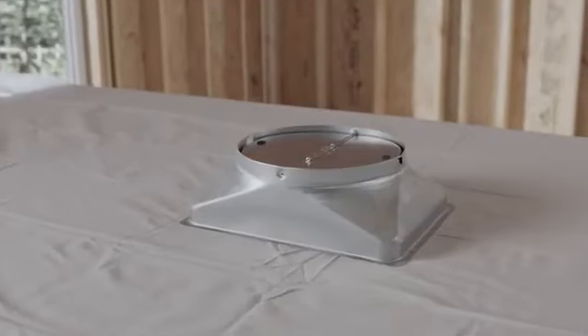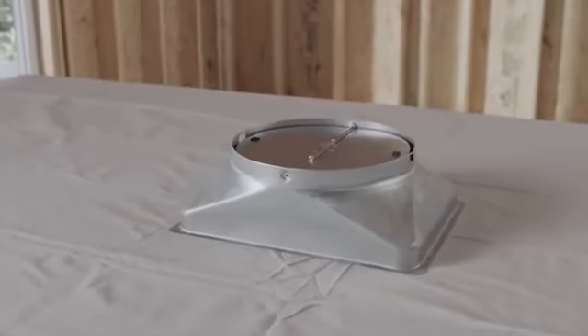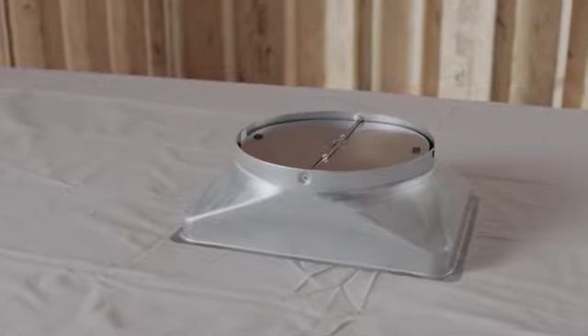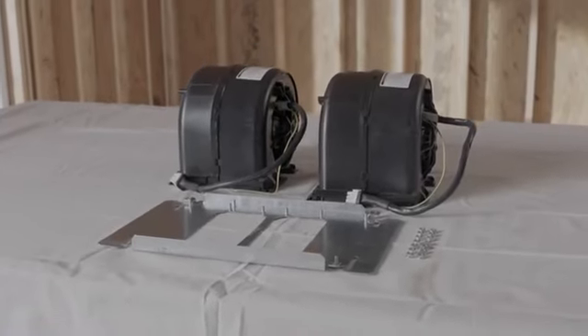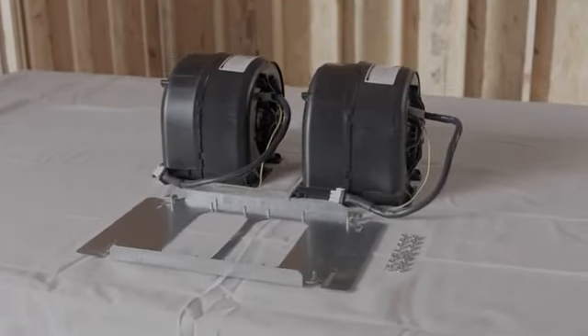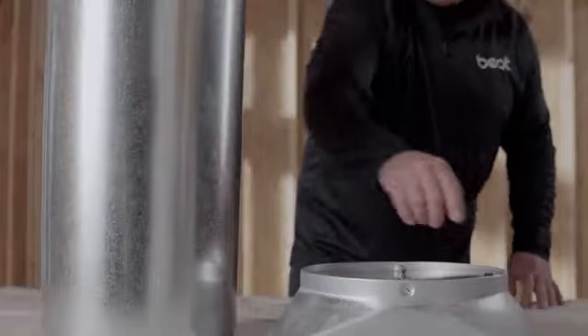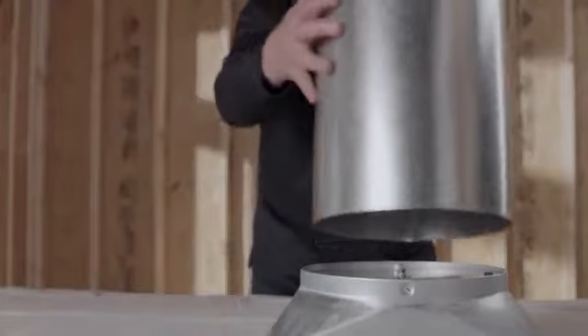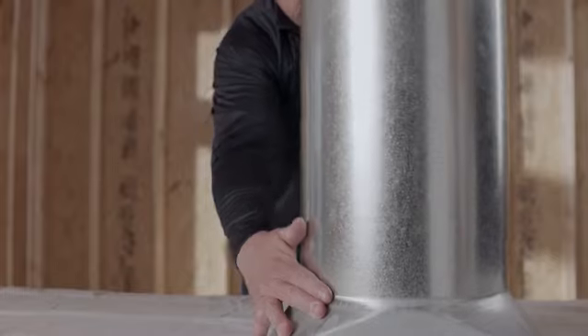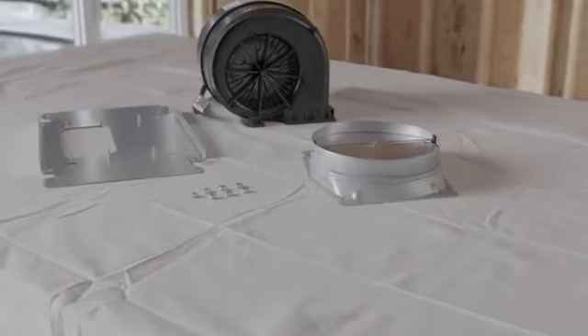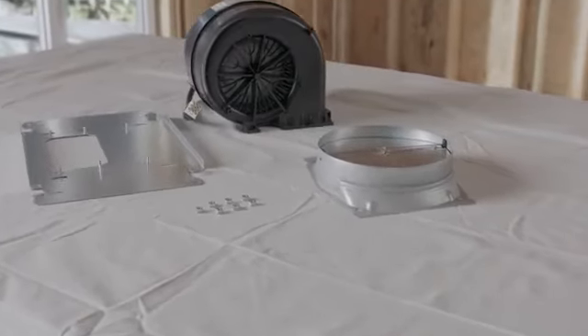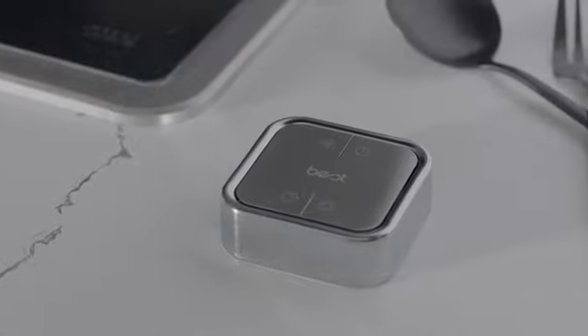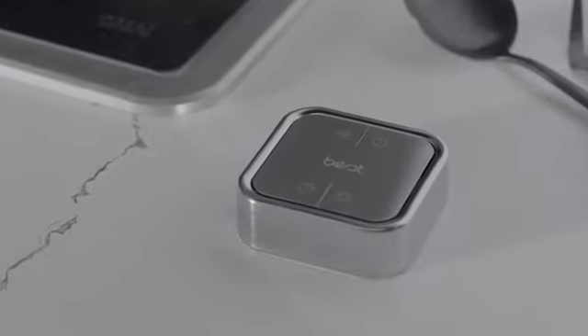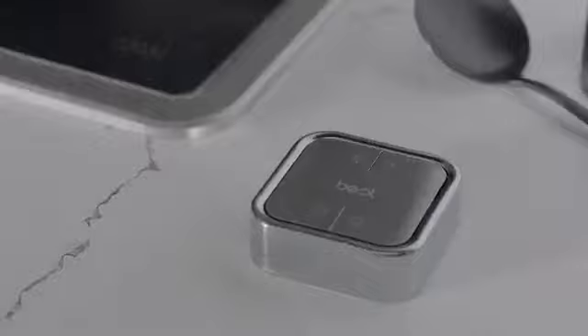The 10-inch damper included with the hood needs to be used for all exterior blower setups. It will also need to be used with the internal PM12 blower. With external blowers, the ducting connects directly to the damper with no rough-in plate required. The 8-inch damper is only needed with the PM6 internal blower. The hood is supplied with a remote to control the unit for ease of operation.